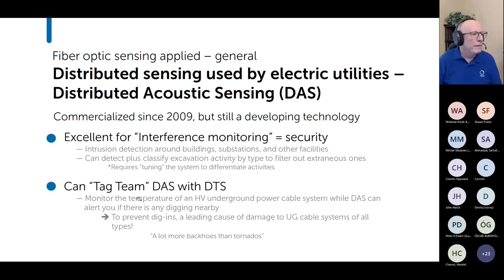And because of this, you can tag team distributed acoustic sensing with distributed temperature sensing. I already talked about this being done often with high voltage underground power cable systems. And the DAS can be added to alert you to any potential digging activity, because those circuits tend to be critical. And it's dig-ins that are a leading cause of damage to all types of underground cable systems. Power cables, fiber optic cables, you name it, gas lines, water lines, anything. And the saying that's been around for a long time about that is in comparison to aerial cable systems, because people intuitively think that underground systems are going to be more reliable than aerial systems, but that's not always the case. And the reason is there's a lot more backhoes than tornadoes.